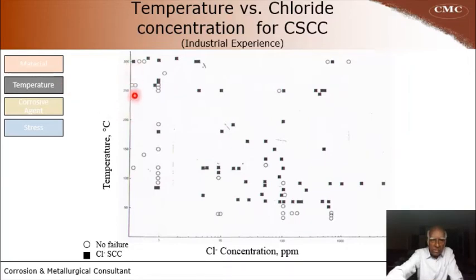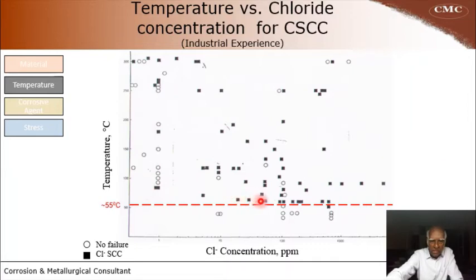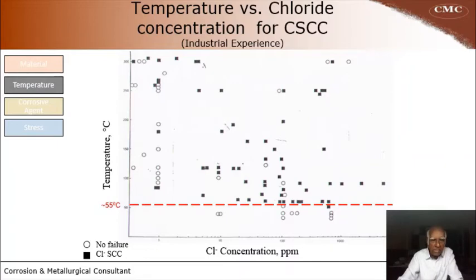The next parameter is temperature. What you see here is a summary of industrial experience — temperature versus chloride concentration for chloride stress corrosion cracking to occur. The dark points show where cracking has occurred. There is a well-accepted minimum temperature of about 55°C below which stress corrosion cracking does not take place. In the present case, our operating temperature of about 170°C is very well above 55°C, so the temperature condition is satisfied.